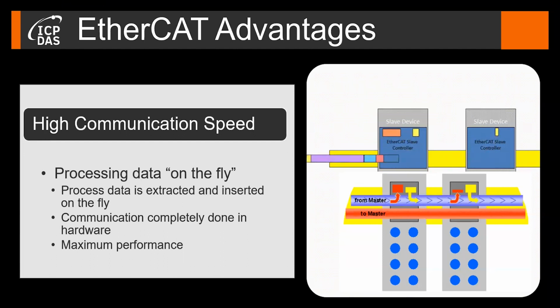Another feature is that data exchange takes place at full frame speed. Processed data is extracted and inserted into the frame while the frame passes through the slave at full speed. The data exchange between slave and frame is completed before the frame moves to the next slave. Another feature of this mechanism is that the slave does not read the entire EtherCAT frame, but only the part of the frame assigned to it during the configuration process. The unique features of the processing on the fly mechanism make EtherCAT communication so fast.